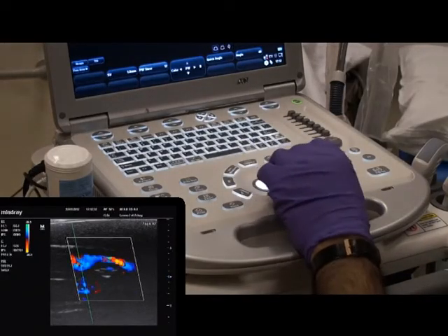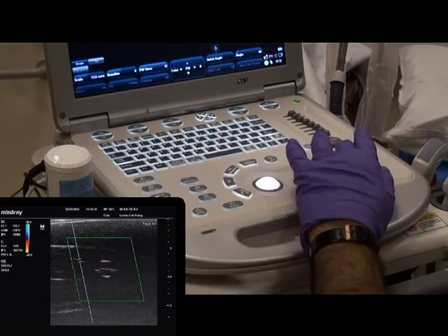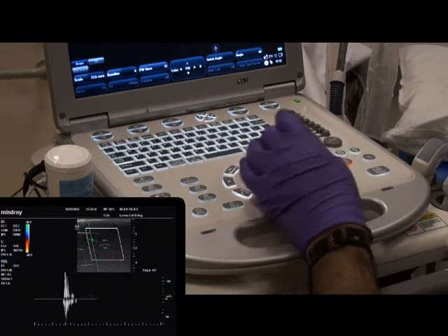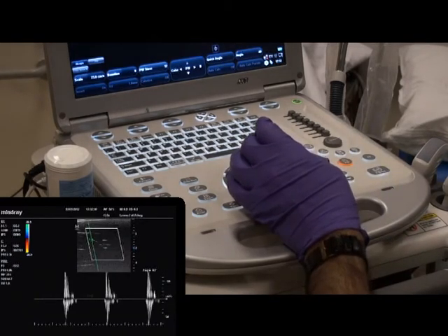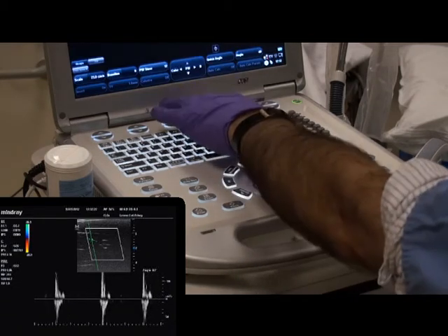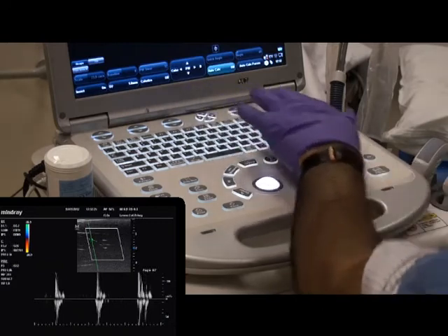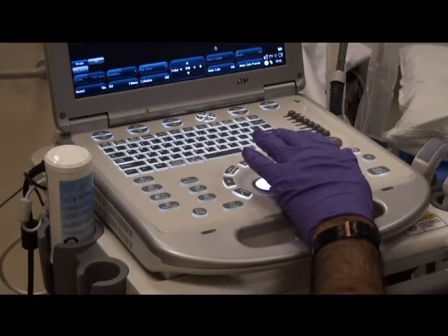Pulse wave spectral Doppler sampling can be done by pressing the PW button to the right of the trackball. This brings up the sample volume. The sample volume can be placed where you want it to sample from. In order to get the tracing, you need to press PW again.